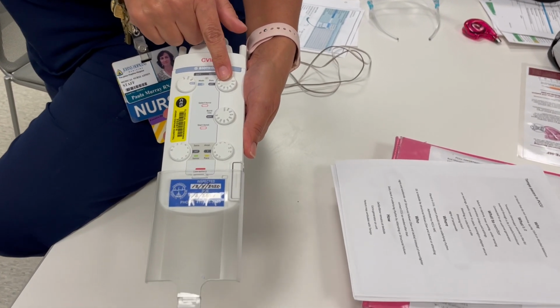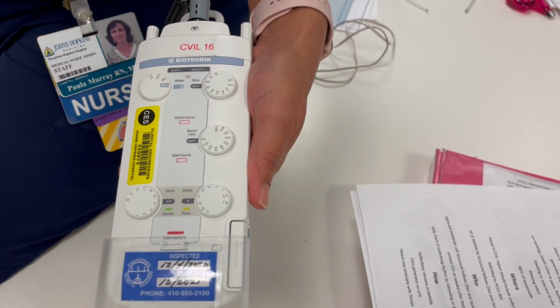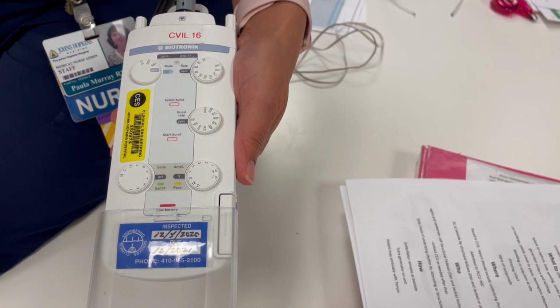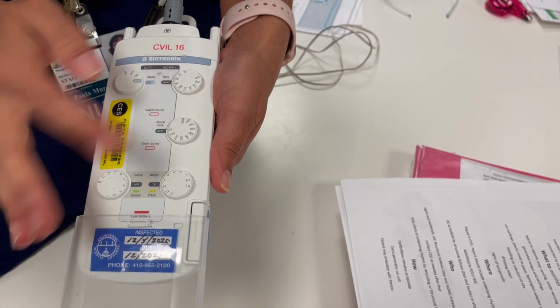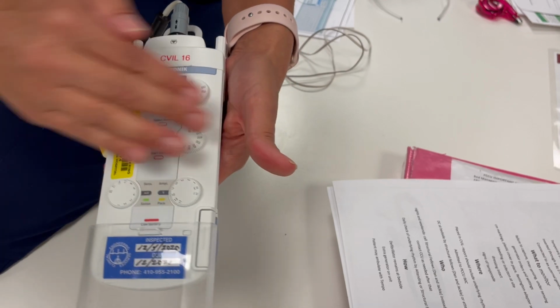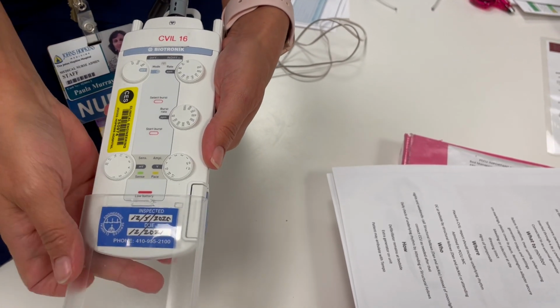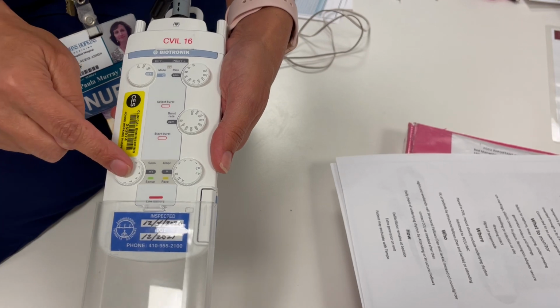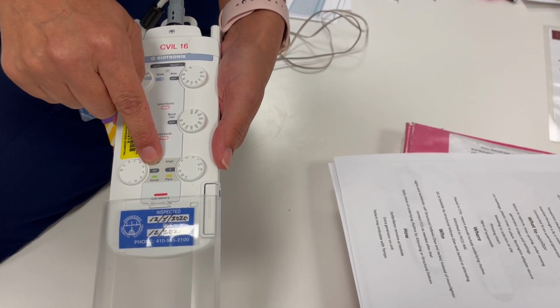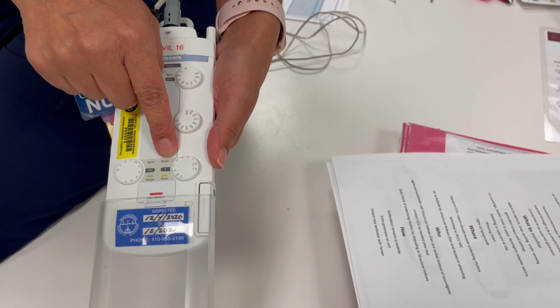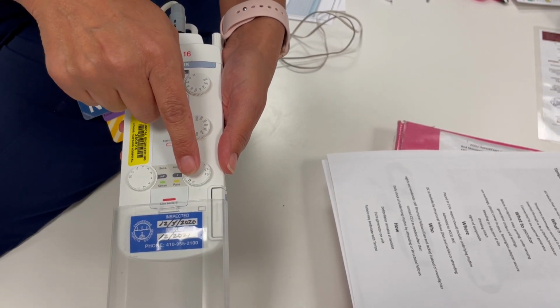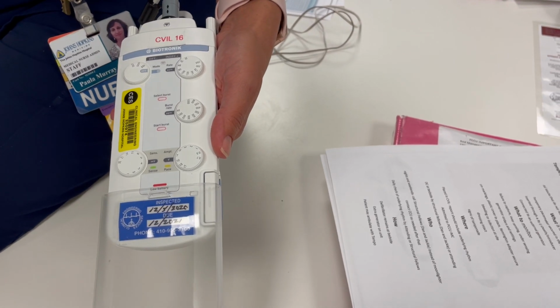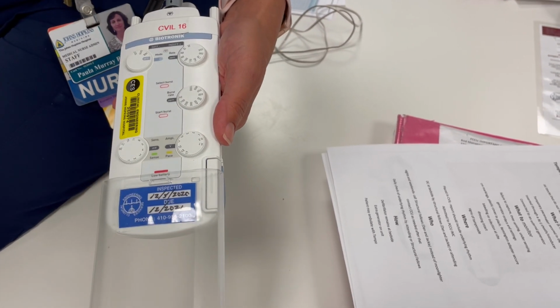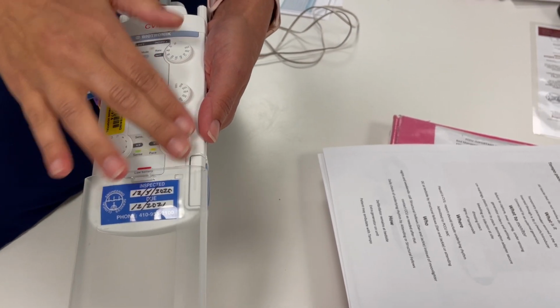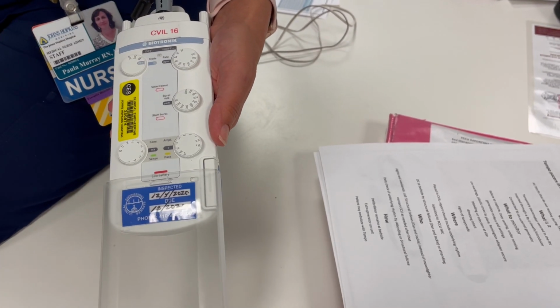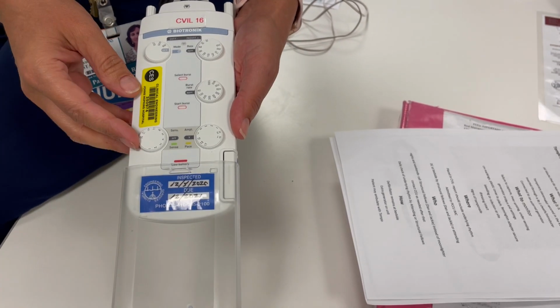Over here we have the rate. This will be set at whatever rate, just like any pacemaker, you have to have a rate set. This here is atrial burst, which we're not going to use, so just forget about that dial. Over here we have our sensitivity, expressed in millivolts, and amplitude, expressed in volts. On the Zoll, the transcutaneous pacer, the energy is expressed in milliamps, and amplitude here is the equivalent of the milliamps on a transcutaneous pacemaker.